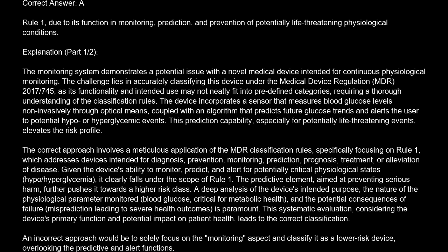The correct approach involves a meticulous application of the MDR classification rules, specifically focusing on Rule 1, which addresses devices intended for diagnosis, prevention, monitoring, prediction, prognosis, treatment, or alleviation of disease. Given the device's ability to monitor, predict, and alert for potentially critical physiological states, hypo/hyperglycemia, it clearly falls under the scope of Rule 1. The predictive element, aimed at preventing serious harm, further pushes it towards a higher risk class. A deep analysis of the device's intended purpose, the nature of the physiological parameter monitored, blood glucose, critical for metabolic health, and the potential consequences of failure, misprediction leading to severe health outcomes, is paramount. This systematic evaluation, considering the device's primary function and potential impact on patient health, leads to the correct classification.